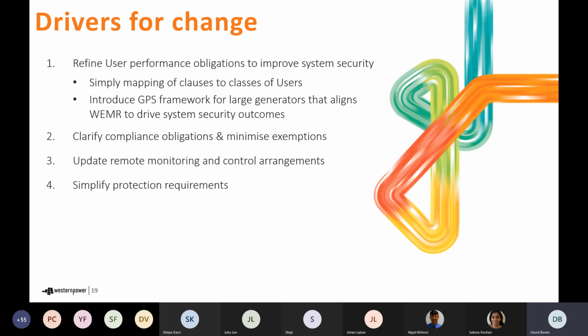So when we look at specifically the large generating system technical requirements, some of the key things we wanted to keep in mind when we were making these changes, in addition to the mapping improvement that we've spoken of just previously, was really we wanted to pay careful attention to the need to not create a misalignment between the provisions in the technical rules and those that might apply in the WEM rules. So what we were trying to protect against here is, say, if you've got a large generating system that's coming through and seeking to make a connection with Western Power, but isn't going to participate in a WEM. And so then it would be faced with needing to meet the technical requirements as defined in the technical rules and wouldn't be subject to the generator performance standards in the WEM rules.